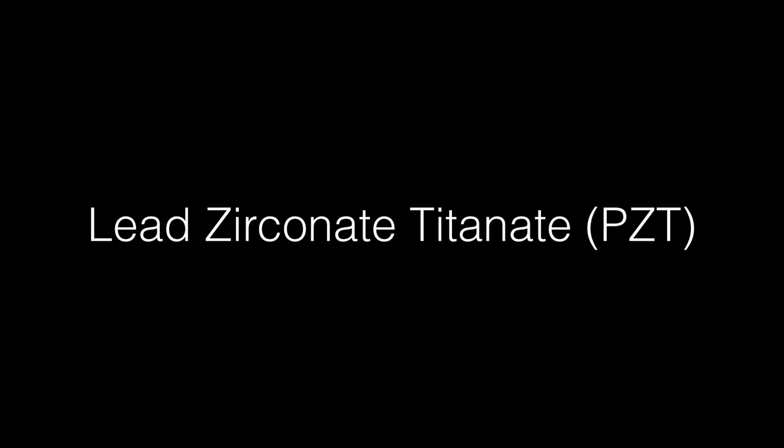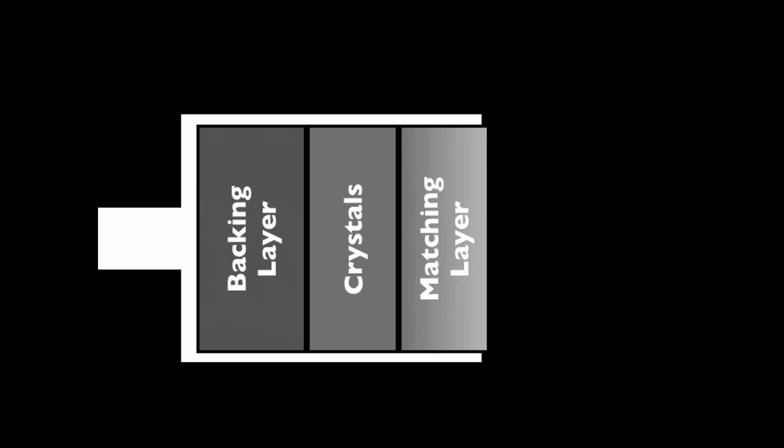Transducers function based on the piezoelectric principle and are a key element of the system — they're also the most expensive and most fragile component. Most modern transducers use synthetic crystals such as lead zirconate titanate. These are heat sensitive and probes should never be autoclaved for sterilization, as heat can misalign the crystals and render the probe useless. The crystals are housed within the transducer with a backing layer behind and a matching layer in front. The backing layer prevents pressure waves from exiting in reverse, directing all sound energy forward. The matching layer reduces acoustic impedance between the crystals and the skin.